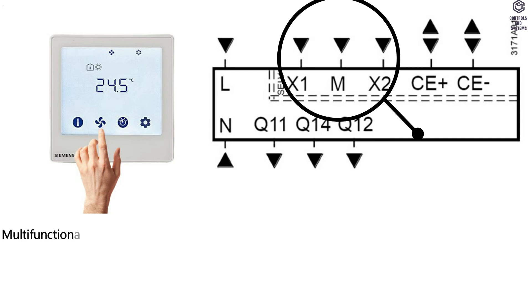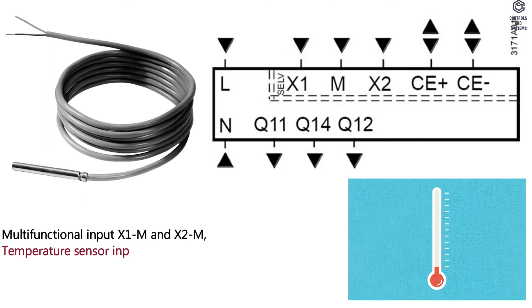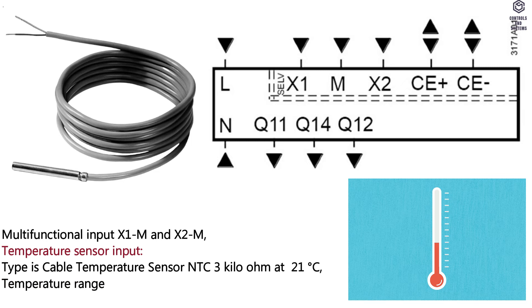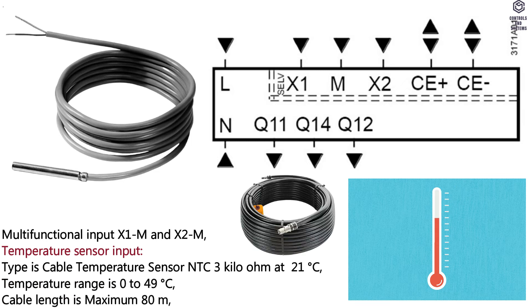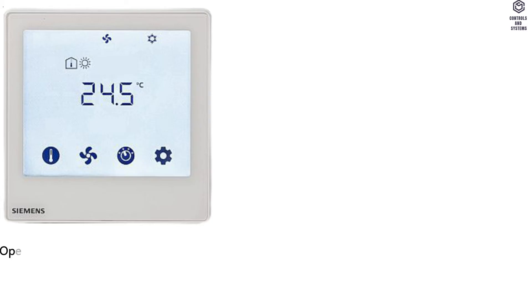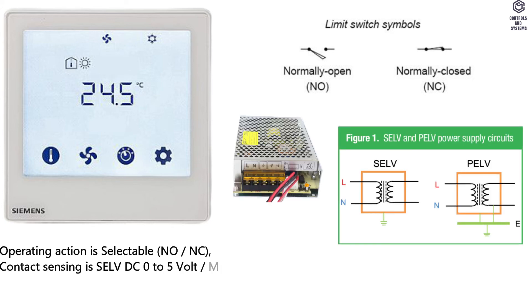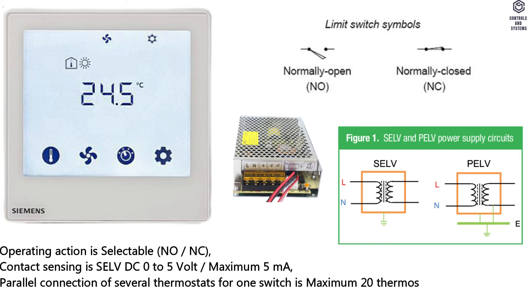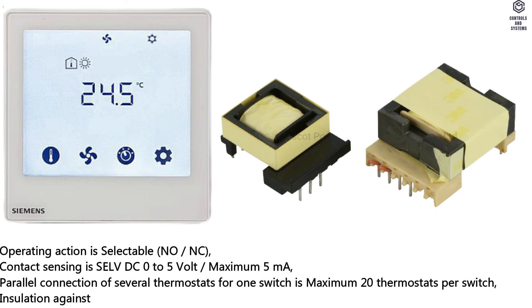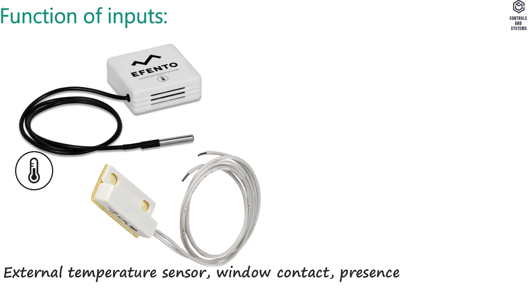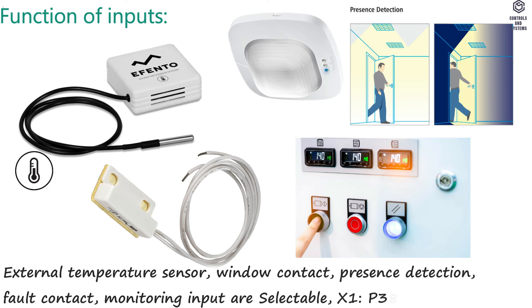Inputs: multifunctional inputs X1M and X2M. Temperature sensor input type: cable temperature sensor NTC 3 kΩ at 21°C, temperature range 0 to 49°C, cable length maximum 80 m. Digital input: operating action selectable NO/NC; contact sensing SELV DC 0 to 5V, maximum 5 mA; parallel connection maximum 20 thermostats per switch; insulation against mains voltage SELV — 4 kV reinforced insulation. Function of inputs: external temperature sensor, window contact, presence detection, fault contact, monitoring input — all selectable.